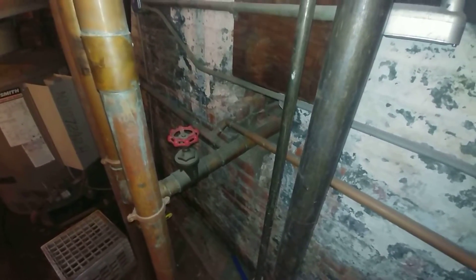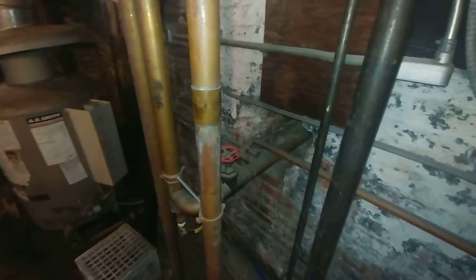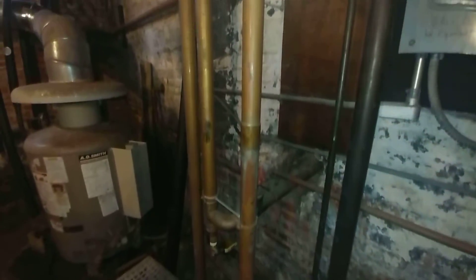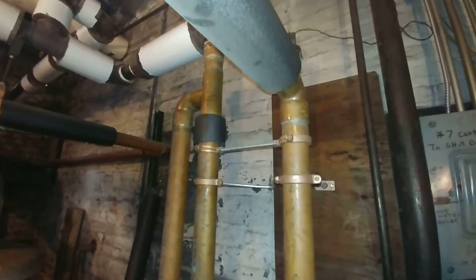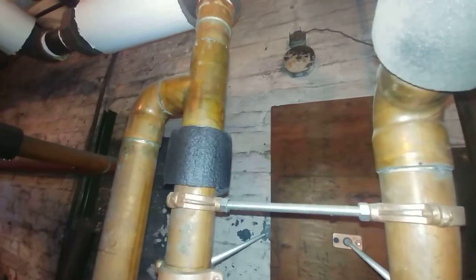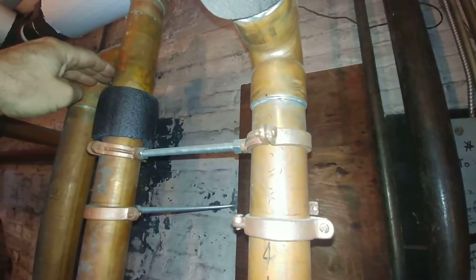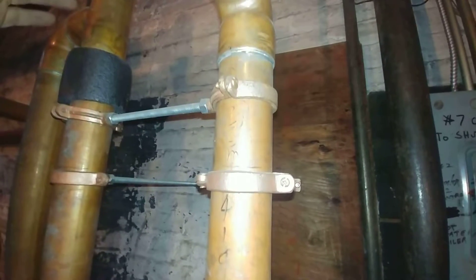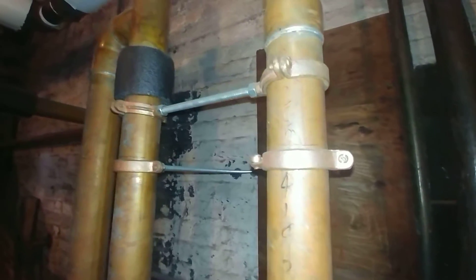In order to keep the steam out of it, we had to flood it. We had to use an old trick called a false water line, and that is what this confusing contraption of pipes is. We measured it several buildings away — this system serves several buildings all connected and fed by the steam system. This more or less duplicates the original water line from the old boilers and makes sure that all the horizontal piping, no matter where it is in the basement, has water in it to keep out the steam, forming a giant loop seal.